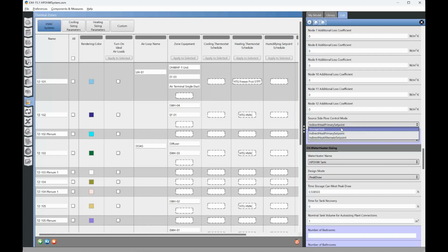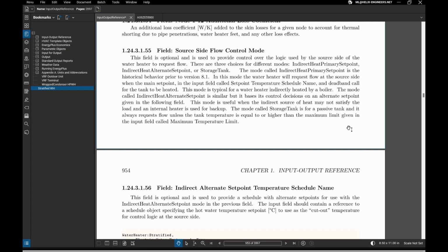The second option is indirect heat alternate set point. You might use that one if the compressor is heating at a lower temperature, and then you have the heating elements bringing the tank up to an even higher temperature. And then there's storage tank solution. This one always requests flow to the compressor unless the tank temperature is meeting the set point. So this has to do with requesting flow to the compressor.